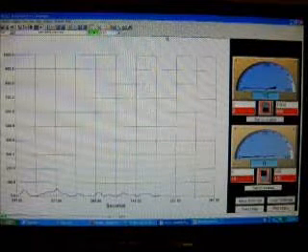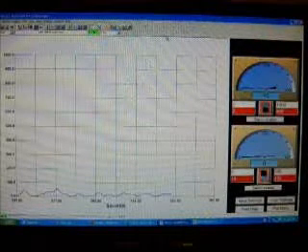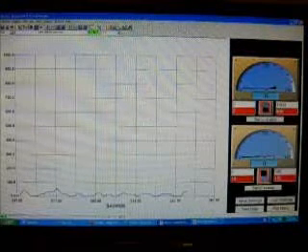Okay, I'm upstairs now just to demonstrate a few other types of things that you can do with this software. Right now I have it on the alarming meter type plotting system. You have an analog meter on the right side of the screen, and you can use that to set alarm points. In this case, I have it set to alarm at points over 900 counts per minute.